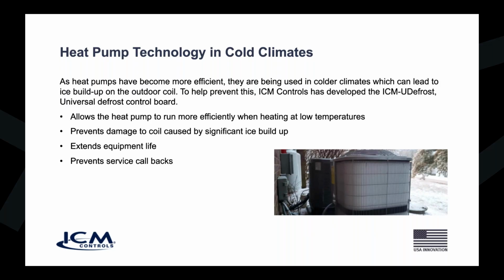Okay, but the problem is with that outdoor coil already being the low temperature coil to begin with, and the indoor coil being the high temperature coil, that low temperature coil on the outside is already cold. Now you're putting it at a low pressure. It's just an avenue for ice buildup. So you need something to defrost that ice.